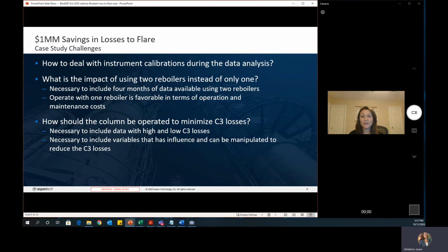Based on operational tests of running 1 reboiler versus 2, they wanted to dive into and understand the results of operating those two different ways. The preference was to operate 1 reboiler rather than 2, both to have a spare for cleaning and to keep favorable maintenance costs. Most importantly, they wanted to determine how to operate in order to minimize those C3 losses.